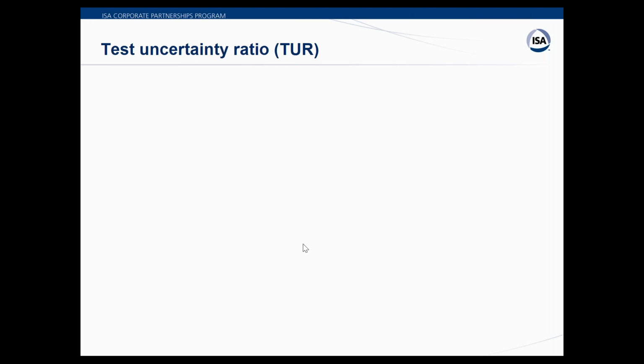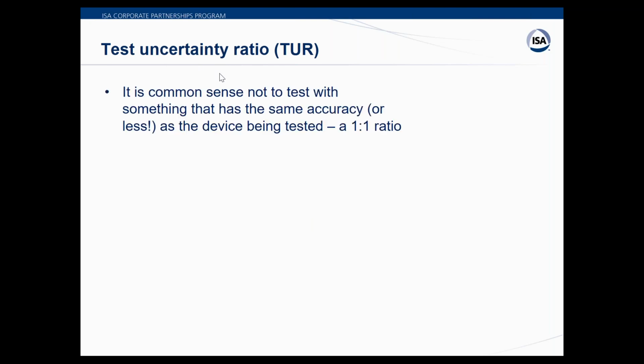So one more acronym, test uncertainty ratio, and there's a related acronym, but let's just focus on our key word today, uncertainty. So the first point is it's just using common sense. You can't test something with a standard that is of the same accuracy class as the instrument you're testing. Which is more accurate, the instrument or the calibration standard?